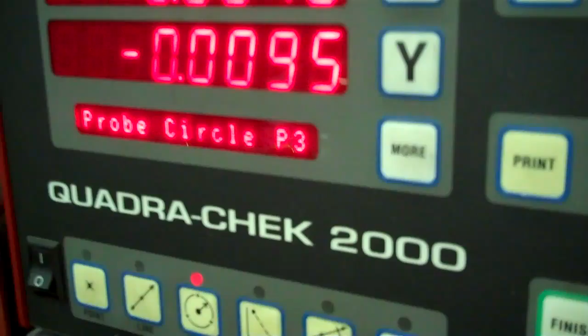So there is a circle button on here. Davey's going to push that circle button. When he pushes the circle, it's going to say probe circle P3, which means 3 points of that arc he needs to probe. So what he's going to do is he's going to come up here and he is going to cross that shadow right there 3 times in 3 places. He crossed it there, he crossed it over on the side, and he crossed it again there.